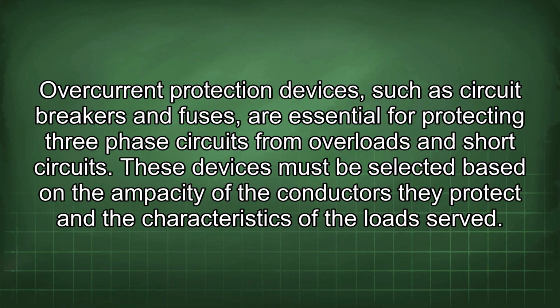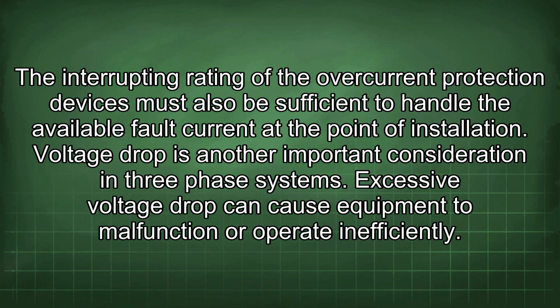requirements. Overcurrent protection devices, such as circuit breakers and fuses, are essential for protecting three-phase circuits from overloads and short circuits. These devices must be selected based on the ampacity of the conductors they protect and the characteristics of the loads served. The interrupting rating of the overcurrent protection devices must also be sufficient to handle the available fault current at the point of installation.